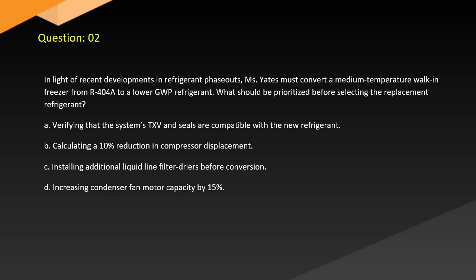Question 2. In light of recent developments in refrigerant phase-outs, Yates must convert a medium-temperature walk-in freezer from R-404A to a low-GWP refrigerant. What should be prioritized before selecting the replacement refrigerant?